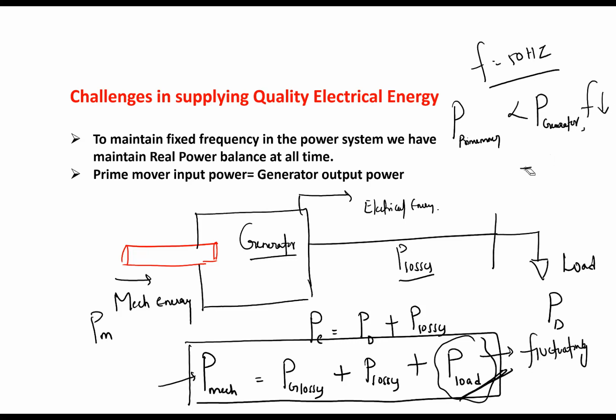Understand? So it is a very big challenge to keep the frequency fluctuation within limits. The main point is to maintain fixed frequency in the power system, we have to maintain real power balance at each and every instant of time. If there is a mismatch, your frequency starts fluctuating. So prime mover input power you have to match with the generator output power. Generator output power depends upon the transmission and distribution losses plus the load connected to the system. I hope everyone understood this. Any doubt you can ask me.